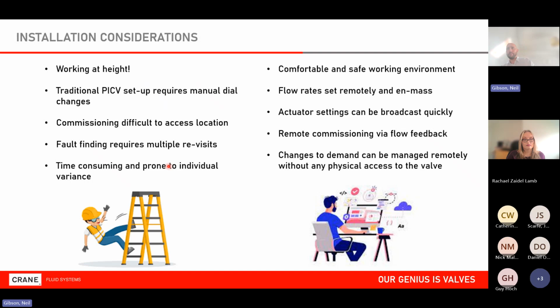So what does this mean? Well, I mentioned going up and down a set of step ladders all of the time. And we often have to do that multiple times as well. Once to turn the dial on the valve, another time so someone can actually put the actuator on the valve, another time so someone can measure the pressure drop across the valve, another time because it wasn't quite right that time, so they need to go back and adjust things slightly.